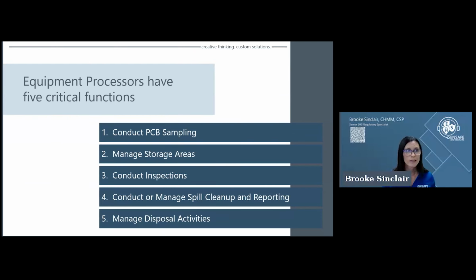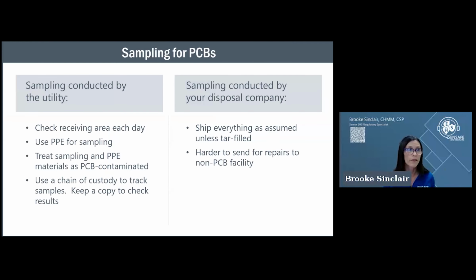For an equipment processor, there are really 5 main areas I see them perform. First, they conduct the PCB sampling. They also manage the storage areas and conduct the inspections. They conduct or manage, if they use a third party, spill cleanup and reporting. And they manage the disposal activities. There's manifest involved, signatures involved, pickup, and then you have to get the certificate of disposal back from your certification company. So those are typically what we see equipment processors do, and again, that's usually the substation groups within most utilities that I work with.